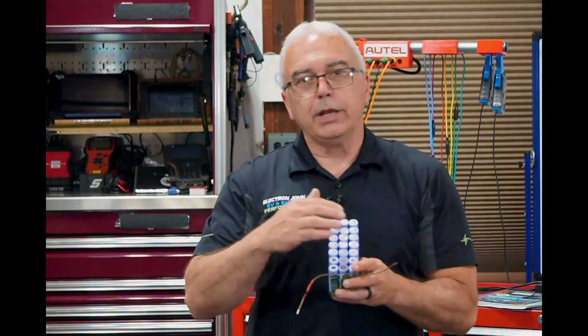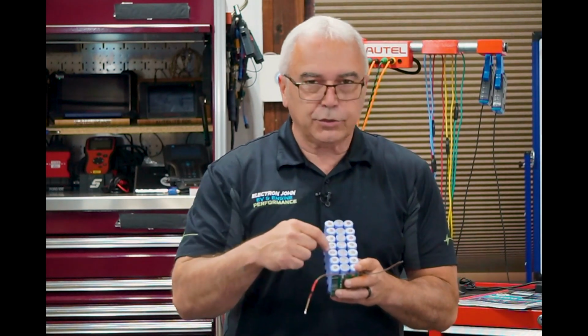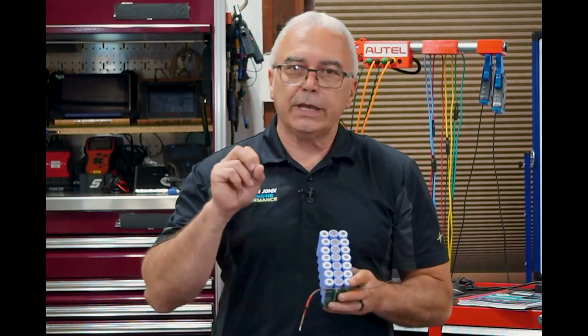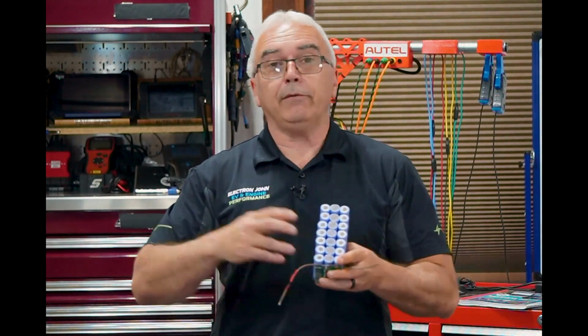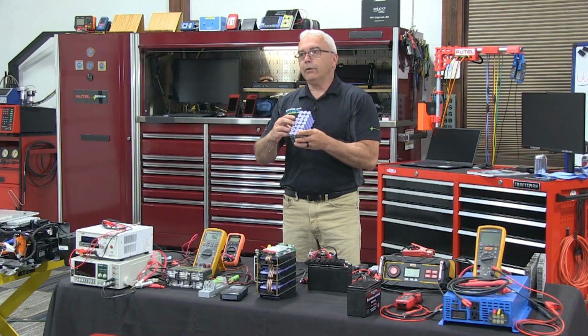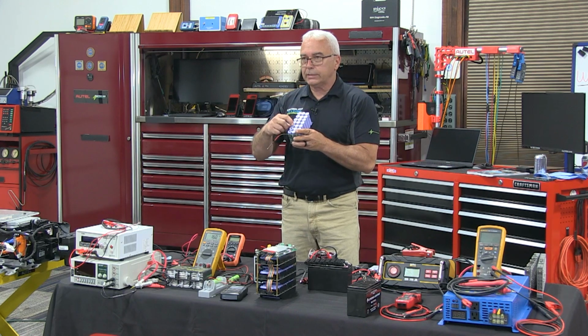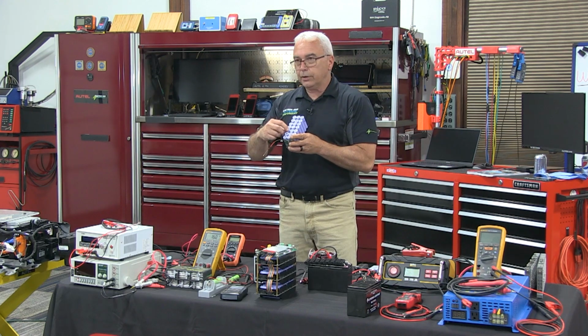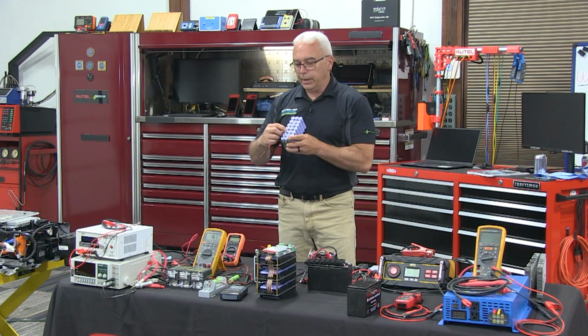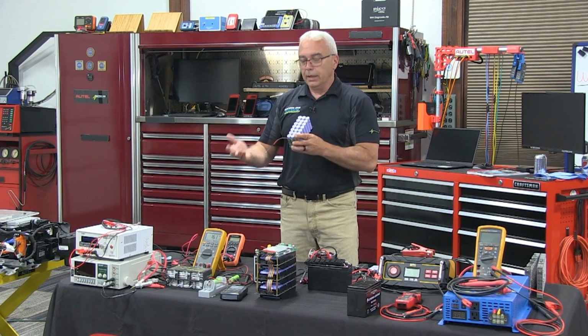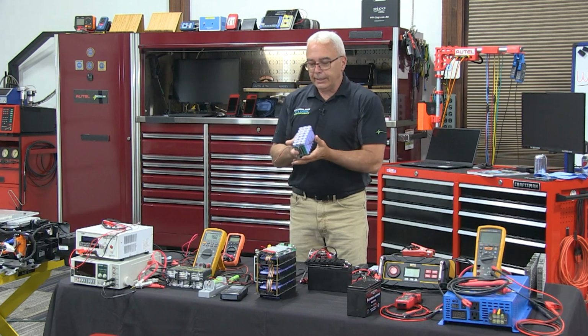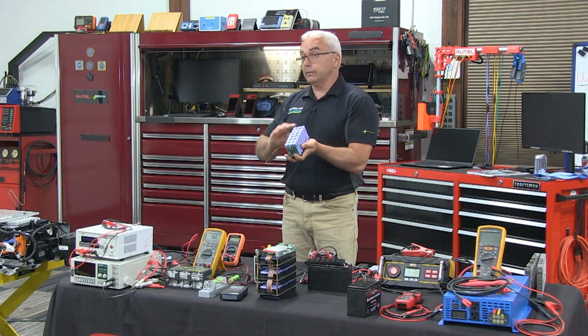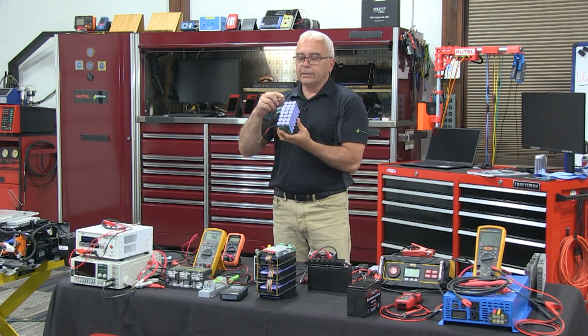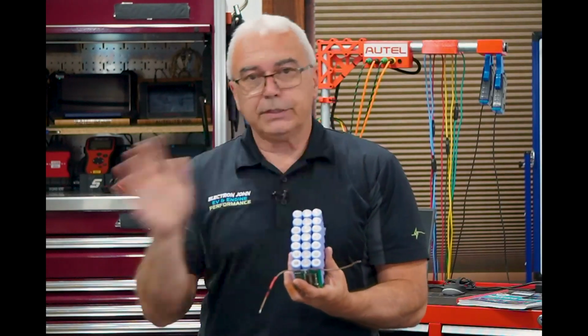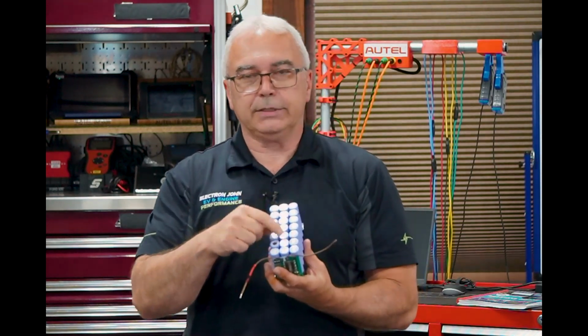So we have voltage, and remember, depending at what stage they're at, we could be at the stage where there's a small short present, which increases the heat, and then eventually we have a larger short internally. As long as there's still voltage present and there's a short, the next one over here goes into thermal runaway. And now this fire starts back up again. It's going to keep repeating until every single cell is extinguished and has zero voltage left inside of it.